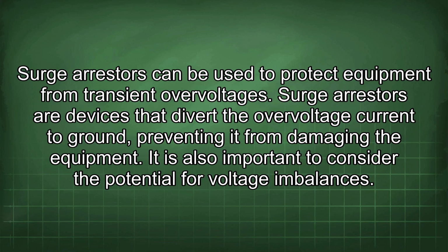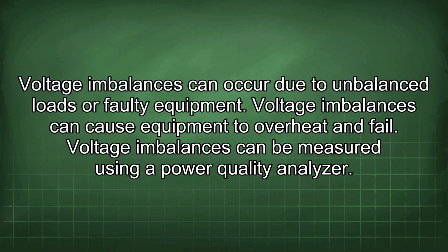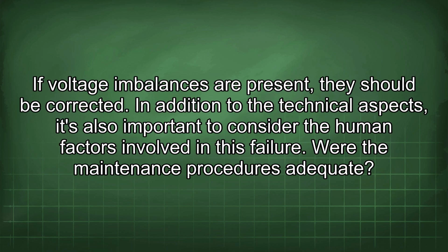It is also important to consider the potential for voltage imbalances. Voltage imbalances can occur due to imbalanced loads or faulty equipment. Voltage imbalances can cause equipment to overheat and fail. Voltage imbalances can be measured using a power quality analyzer. If voltage imbalances are present, they should be corrected.